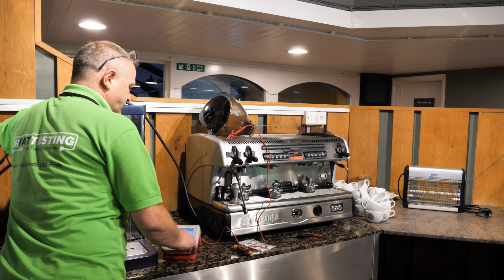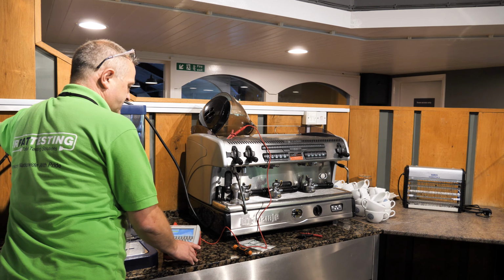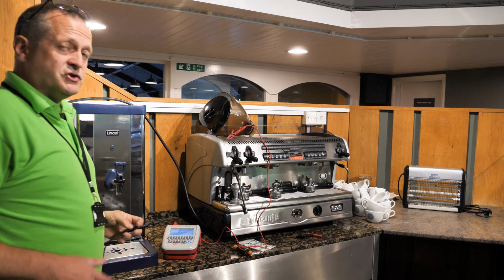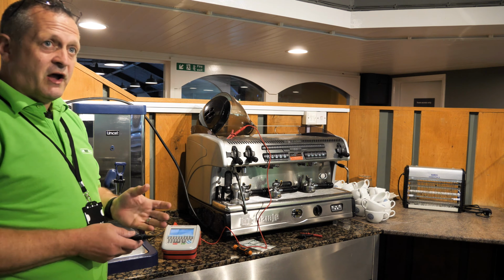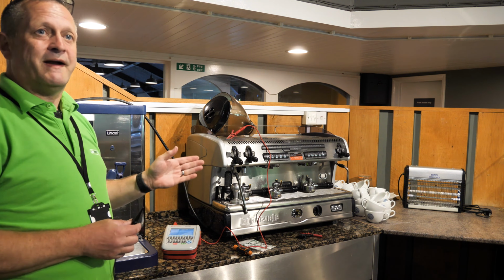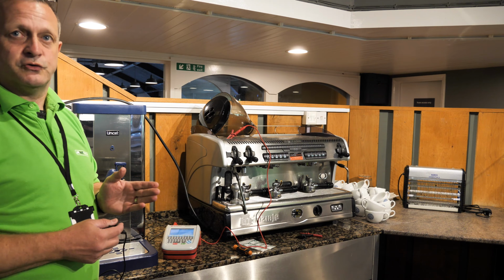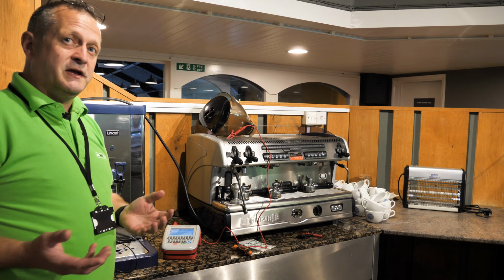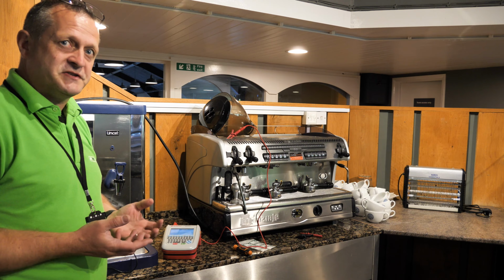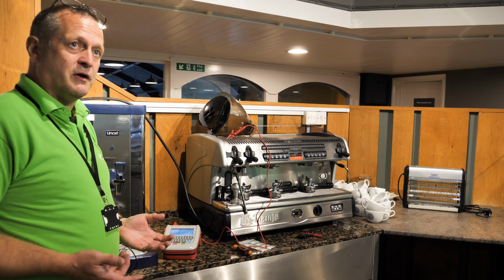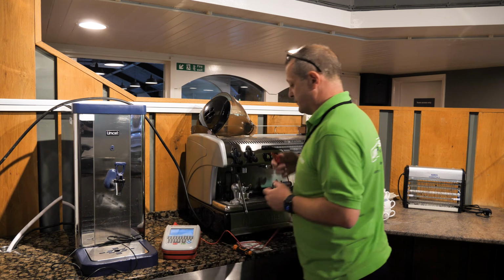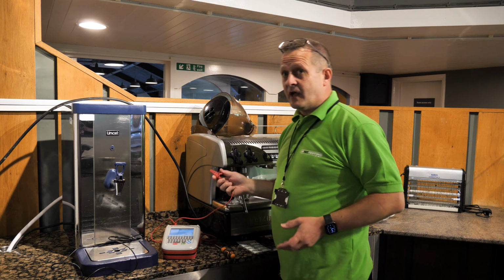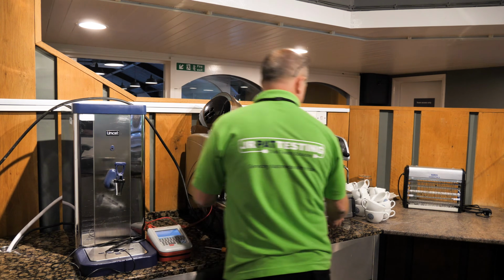The machine is making sure that I'm away from the device, conducting the test. Now, on that particular occasion, it's showing a fail. It's probably not a real fail, it's probably because I've not found the right metal part to conduct the test with. So don't automatically record it as a fail, look for another metal part to actually conduct the test with.